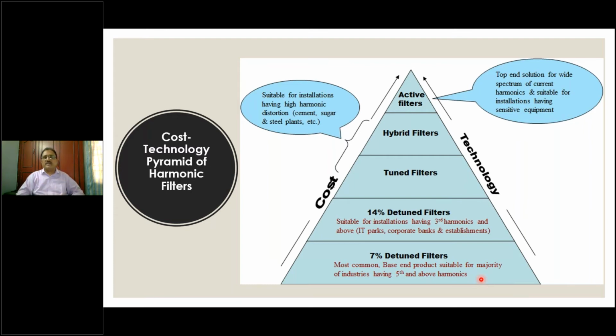technology pyramid based on the cost. So typically 7% detuned filters will be the first level of investment, or if it's a third order harmonic like IT parks and corporate banks, 14% detuned filters will be the solution. Tuned filters is again a solution available, costlier than these two, and still costlier will be hybrid. And then the best in class is the active filters. And today we have other technologies like active front end, and so on and so forth. So a typical cost pyramid will look like this.